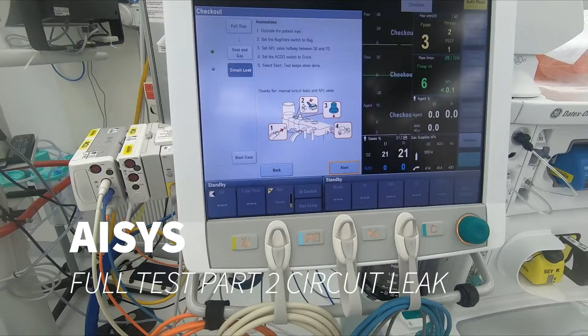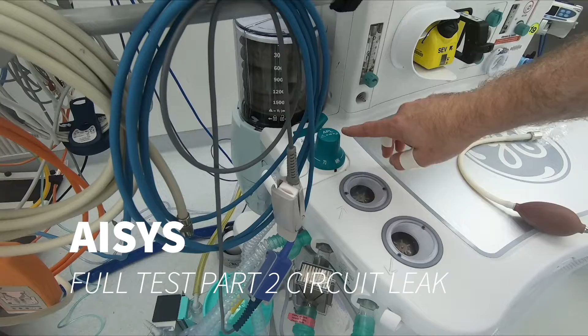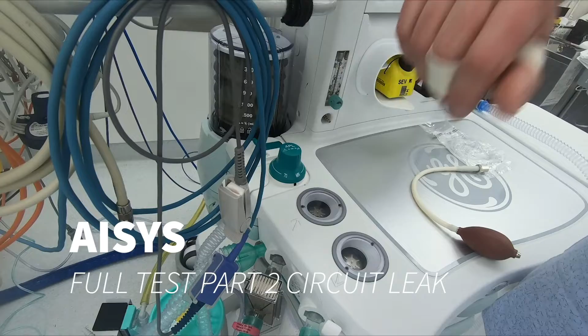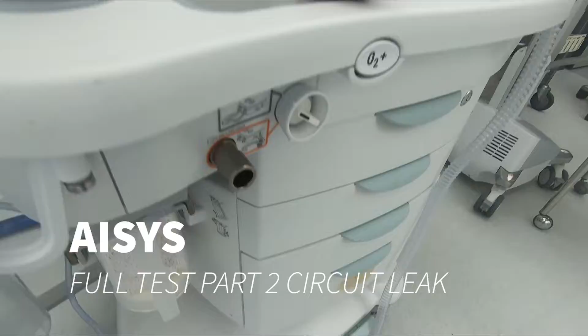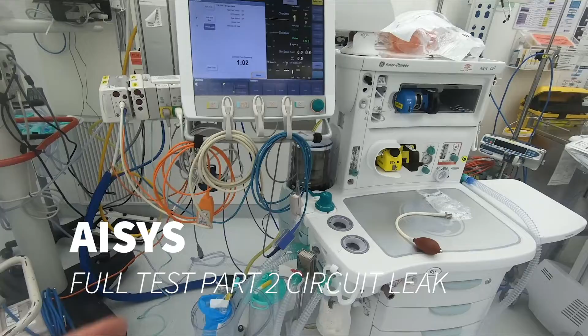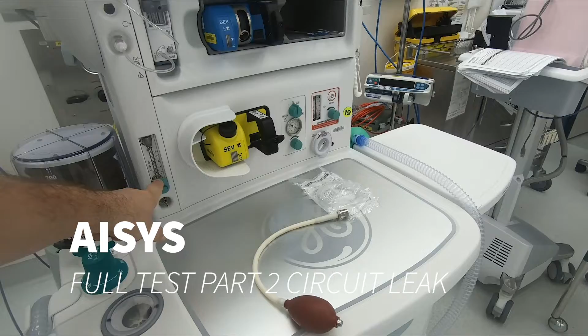I'll pause it. Yep. So it's finished. Occluded patient Y, still occluded. The bag is on the left, done. APL halfway between 30 and 70. ACGO is still to circle. There's that one there. Select start. So I'm ensuring this is a leak test with your 30 and 70. And I'm checking that your APL is calibrated reasonably.